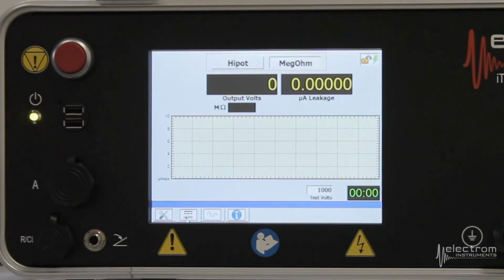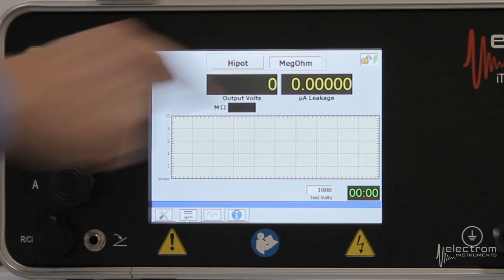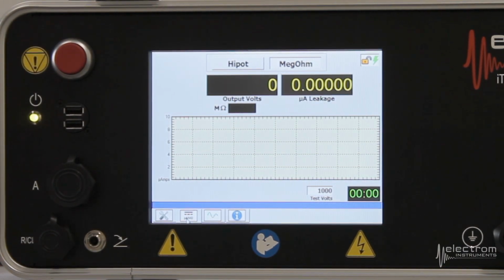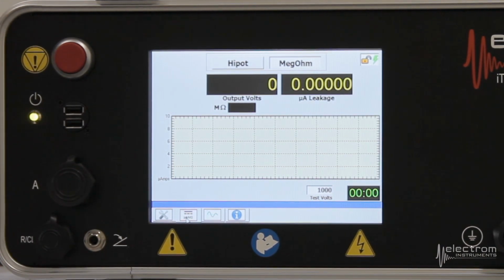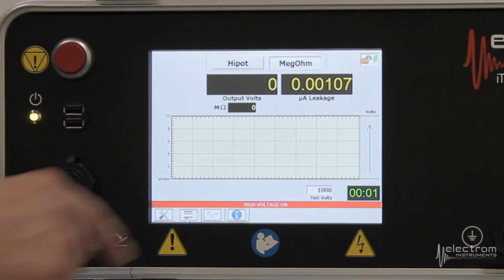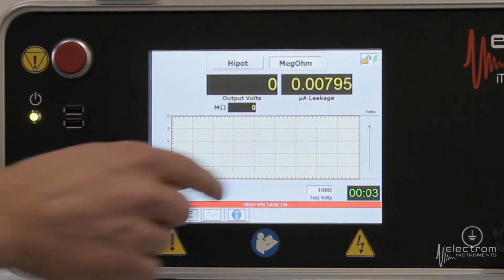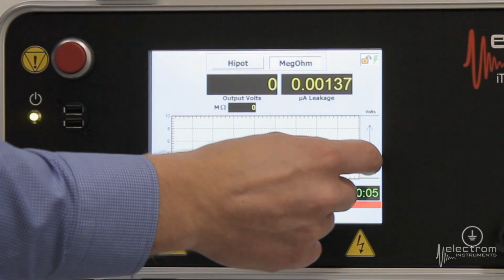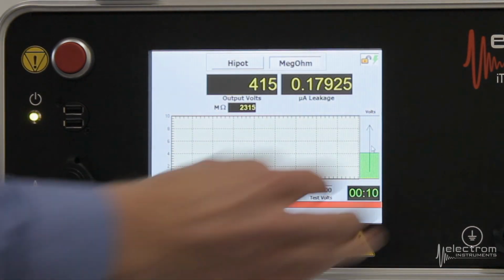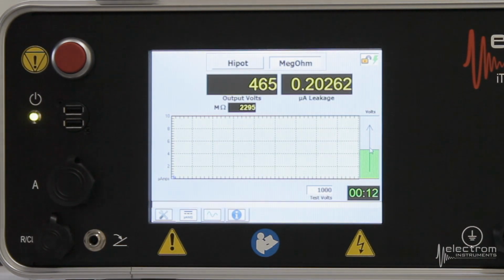First up here is the Megohm measurement. So we will click the red button and we will increase the voltage. In this case we're going to bring it up to 500 volts actually. And look at the microamp leakage current as well as the Megohm reading. So press the red button, high voltage is on, and now we use the slider on the right hand side of the screen. So bring it up here slowly and try to get to about 500 volts.